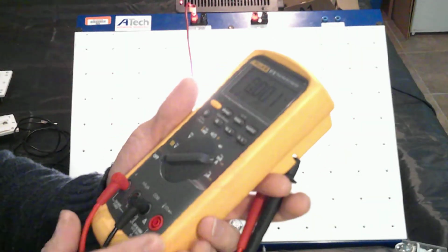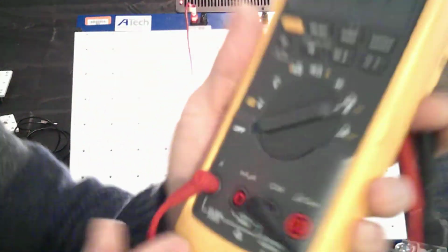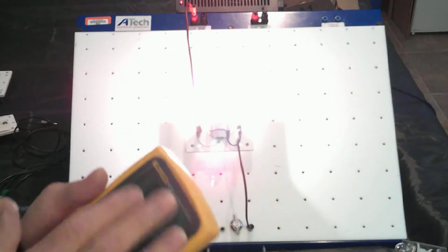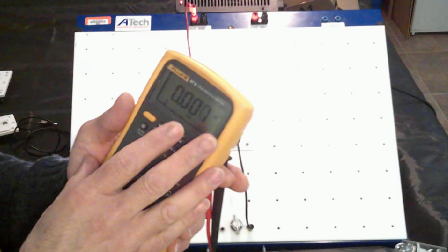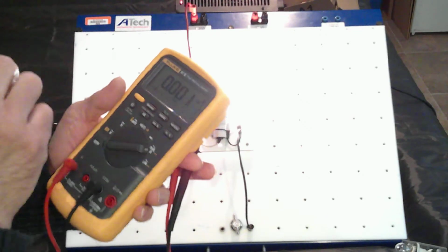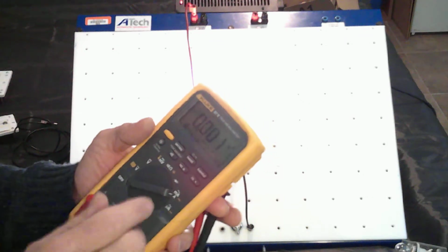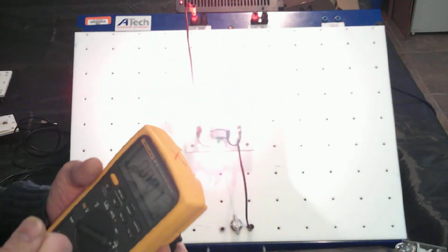The meter is protected to 10 amps maximum. So if we were to measure something that was more than 10 amps of rating, we would hurt the meter. If we hurt the meter, a fuse blows inside that costs about $17. What we're going to do is, if we know we're well below 10 amps, we can run it through the meter. If we can't, we have to use what's called an inductive pickup, where we wrap it around the wire and we pick up the magnetic field of that wire, and we can get an accurate reading. Right?